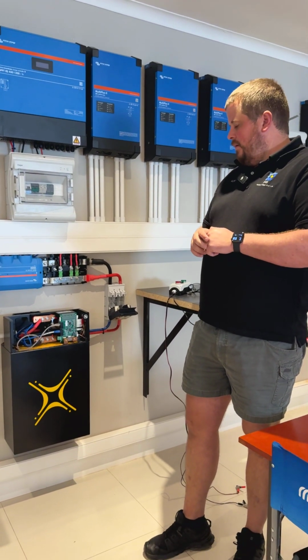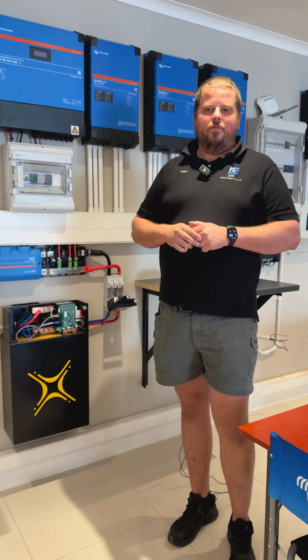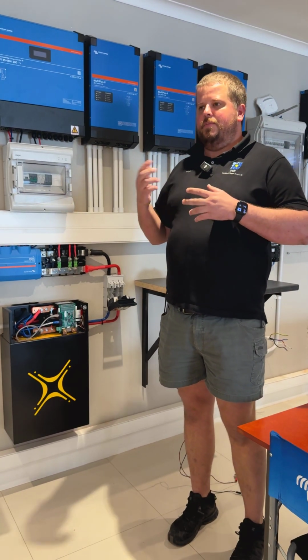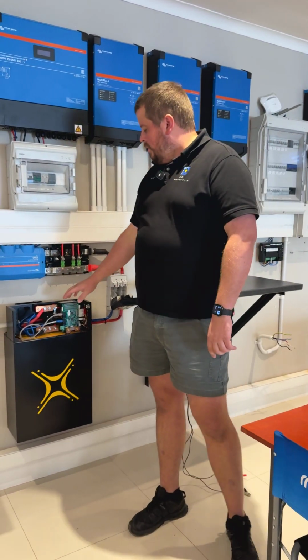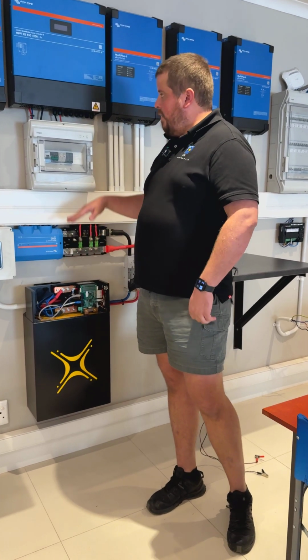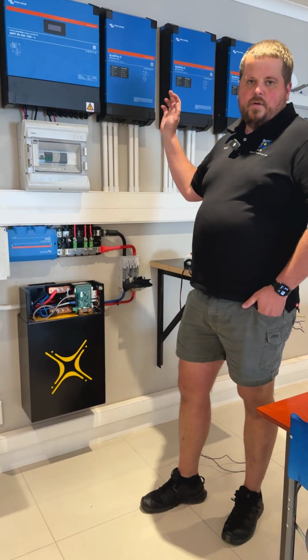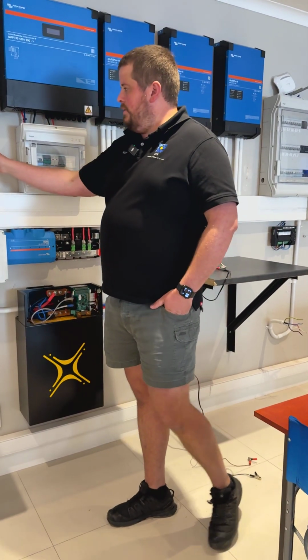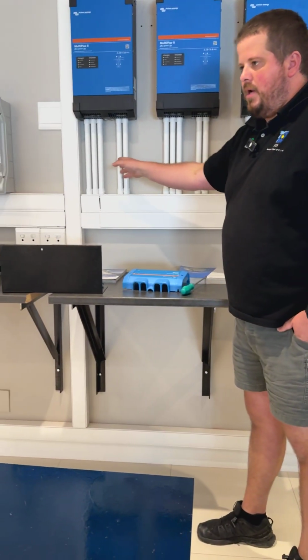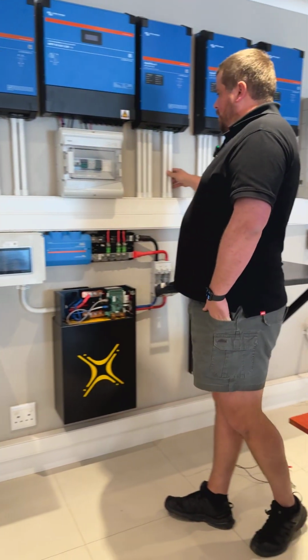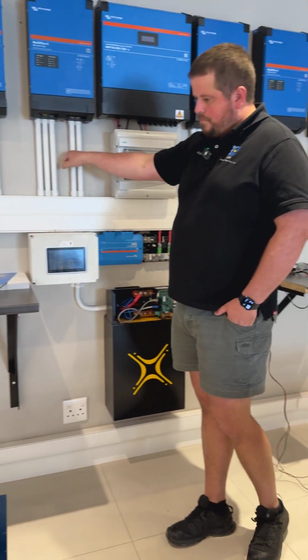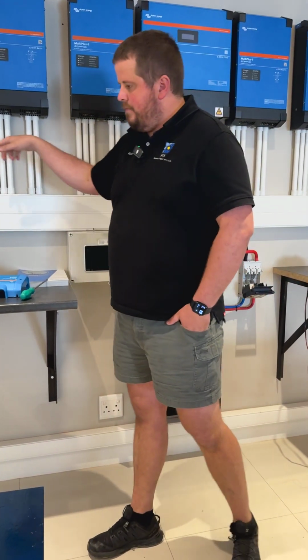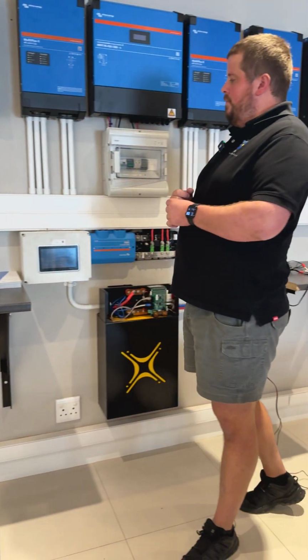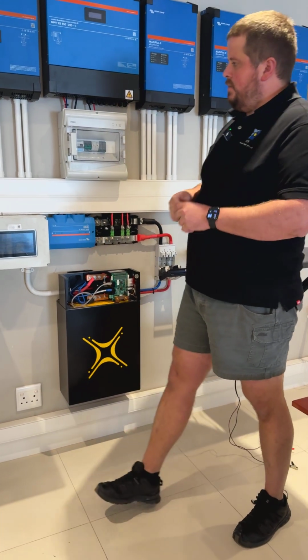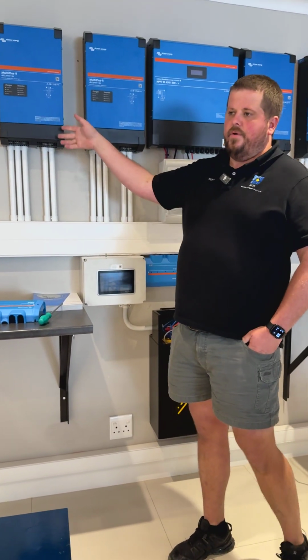We work with quite an interesting thing. My practice, out of experience, is to pre-charge from your battery bank to your inverter bank. This installation doesn't have it on because this is for training purposes. Most guys install pull fuses at each inverter - that is correct, I don't blame them, I believe it's also correct practice because you can isolate the inverter if you want to work on it.